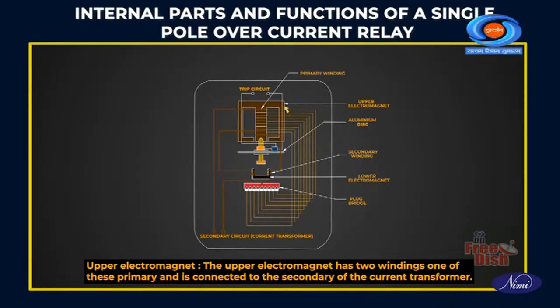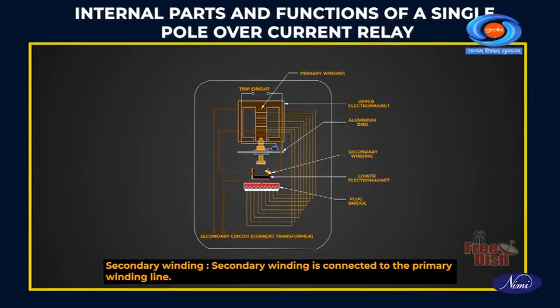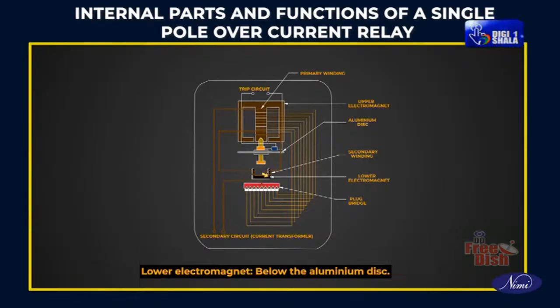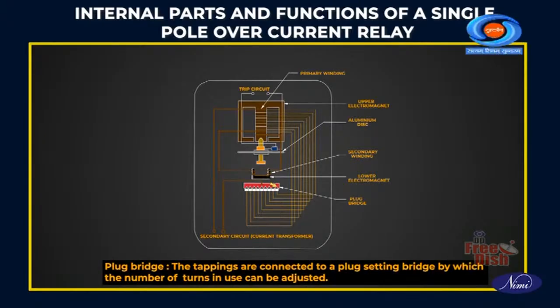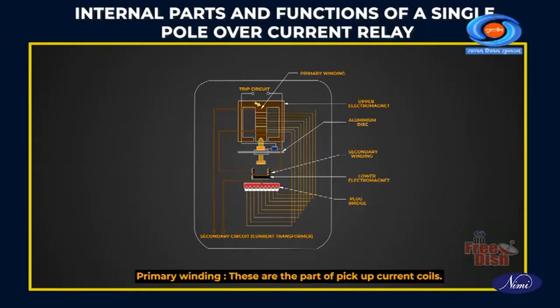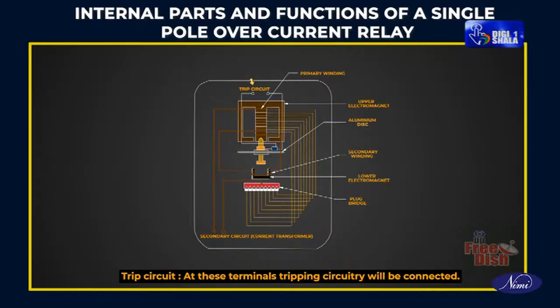The upper electromagnet has 2 windings. One of these is primary and is connected to the secondary of the current transformer. Secondary winding: the secondary winding is connected to the primary winding line. Lower electromagnet: below the aluminium disc. Plug bridge: the tappings are connected to a plug setting bridge by which the number of turns in use can be adjusted. Primary winding: these are part of the pickup current coils. Trip circuit: at these terminals, tripping circuitry will be connected.